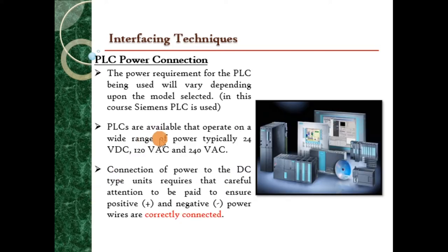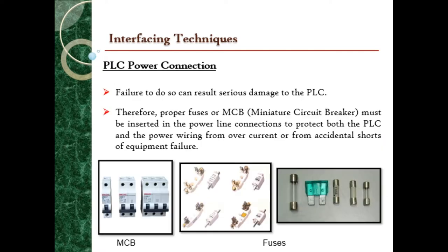So we look into the PLC power connection. In current PLCs, the operating voltage might be 24 volt DC or maybe 120 or 240 volt AC. All of these connections to the PLC must be correctly connected to ensure the safety of the whole operation system. If we fail to provide a safe connection from the power to the PLC, it might cause serious damage to the PLC. Therefore, we need to use proper fuses or maybe an MCB, a miniature circuit breaker, inserted in the power line connections to protect both the PLC and the power wiring from overcurrent or from accidental shorts of equipment failure.